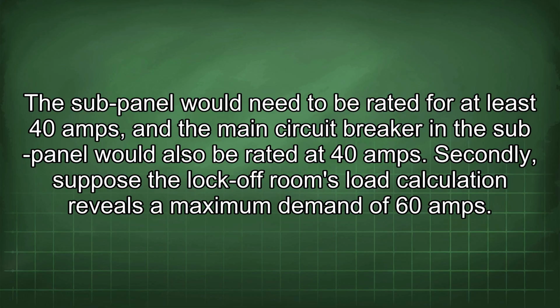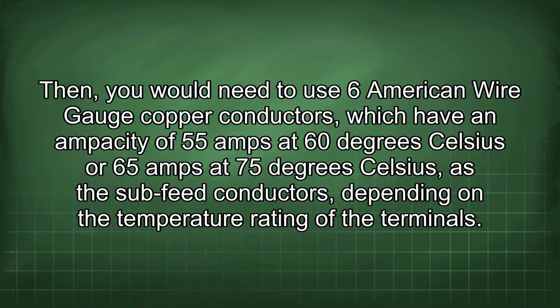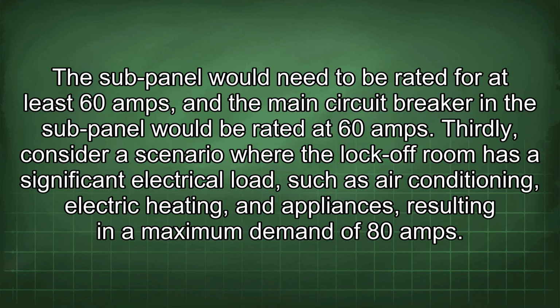Secondly, suppose the lock-off room's load calculation reveals a maximum demand of 60 amps. Then, you would need to use 6 American wire gauge copper conductors, which have an ampacity of 55 amps at 60 degrees Celsius or 65 amps at 75 degrees Celsius as the sub-feed conductors, depending on the temperature rating of the terminals. The sub-panel would need to be rated for at least 60 amps, and the main circuit breaker in the sub-panel would be rated at 60 amps.